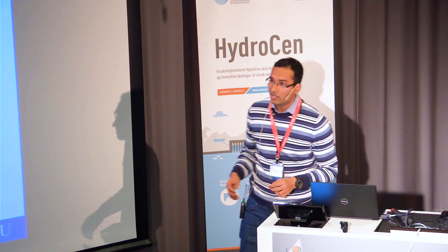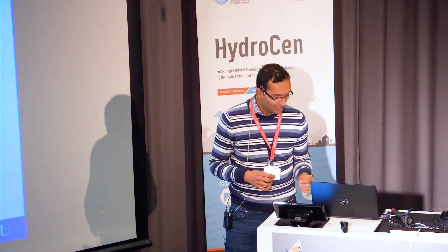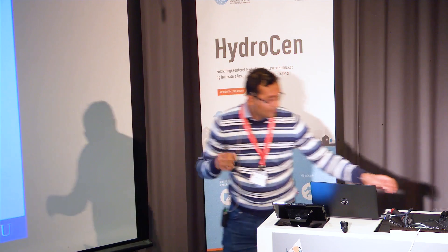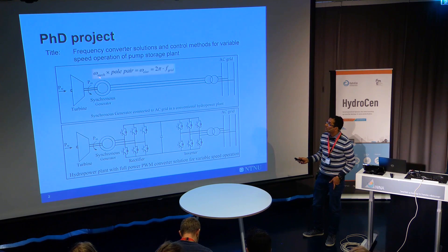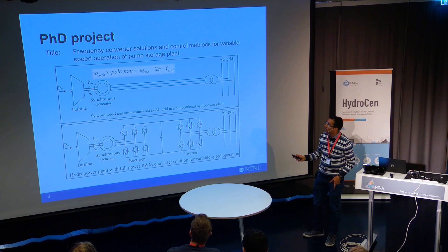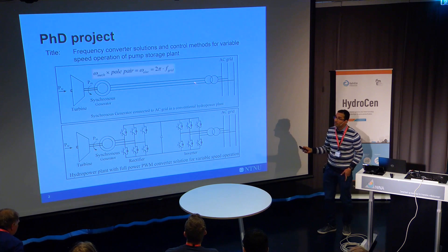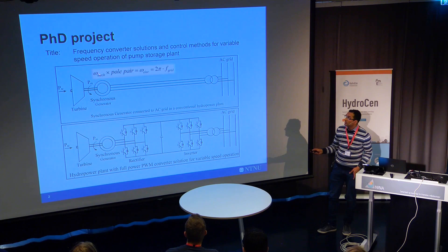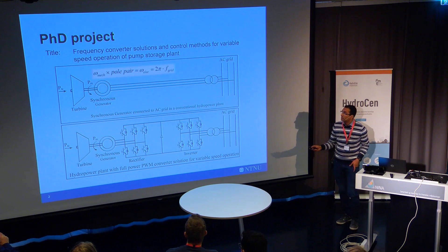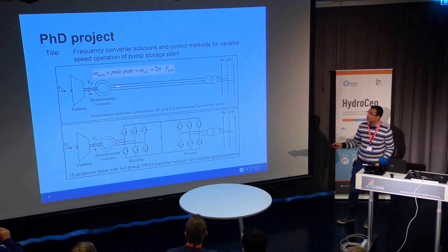I'll explain how we can execute that from an electrical perspective. The relation between electrical and mechanical speed is as follows: we run the turbine at mechanical speed, and the number of pole pairs decides the frequency of the grid. So we mostly run at constant speed, the frequency of the grid remains constant, and the synchronous machine is connected directly to the grid.